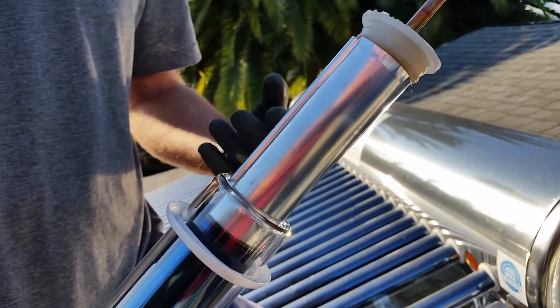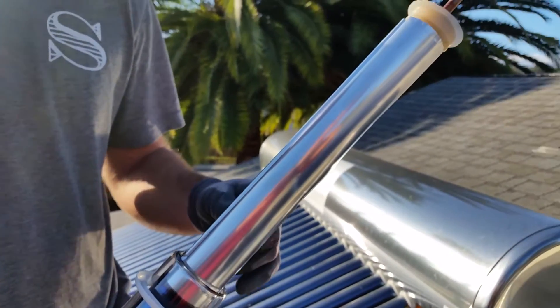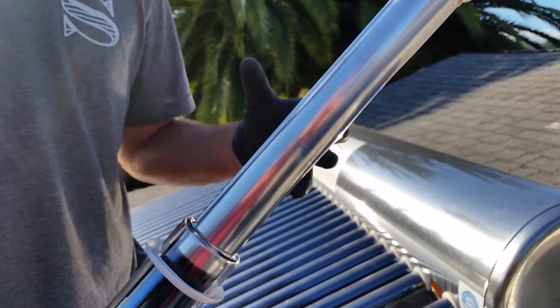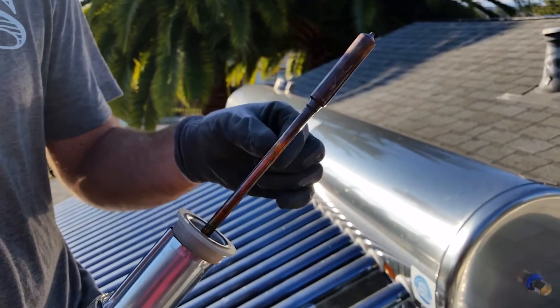The second important feature of the vacuum tube is that it has an aluminum fin assembly which runs the entire length of the tube. This aluminum assembly touches the inner walls of the tube, transferring all that heat into the copper heat pipe, which is arguably the most important part of the design.